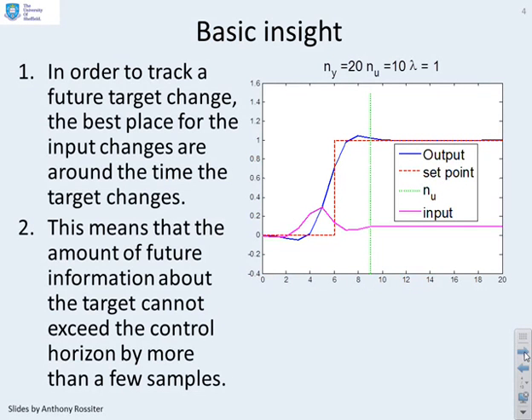The bottom line is we really want the input changes of our degrees of freedom in the predictions to span where the key target change happens. You can see there's the key target change, and I've got my input degrees of freedom here to span that. Here I've taken nu equals 10, which is quite large, but I've started at this point here. The set point change is only six samples into the future, and therefore I'm able to come up with an input trajectory which is appropriate for tracking this particular target.